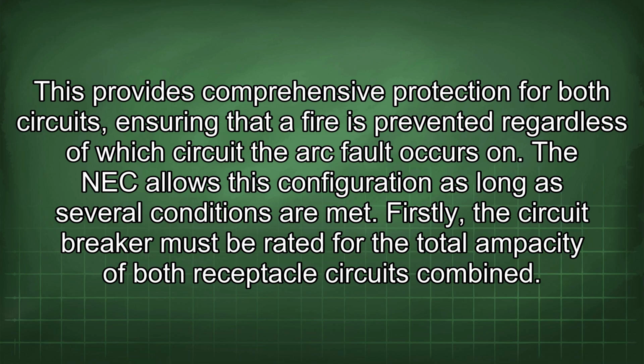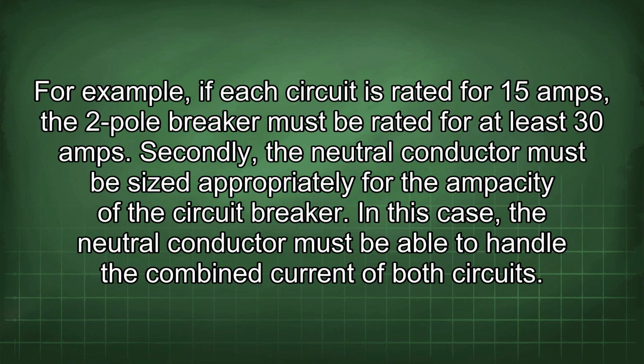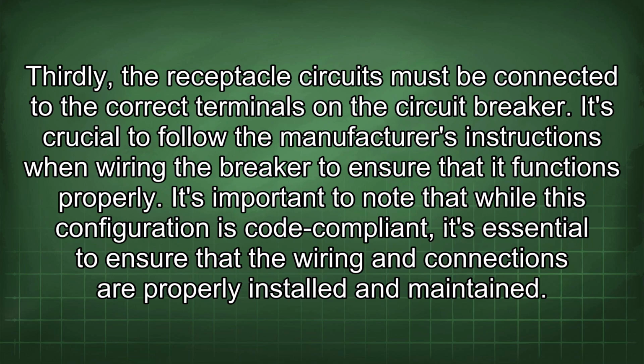Firstly, the circuit breaker must be rated for the total ampacity of both receptacle circuits combined. For example, if each circuit is rated for 15 amps, the two-pole breaker must be rated for at least 30 amps. Secondly, the neutral conductor must be sized appropriately for the ampacity of the circuit breaker. In this case, the neutral conductor must be able to handle the combined current of both circuits. Thirdly, the receptacle circuits must be connected to the correct terminals on the circuit breaker. It's crucial to follow the manufacturer's instructions when wiring the breaker to ensure that it functions properly.